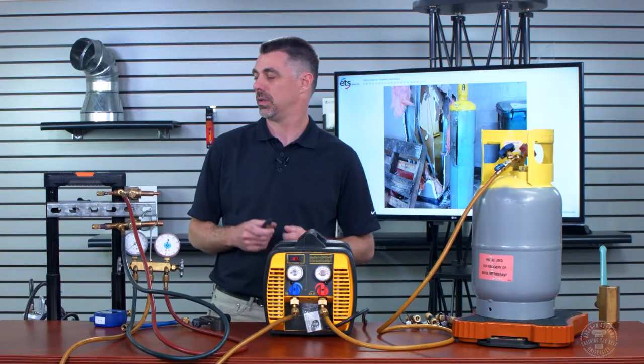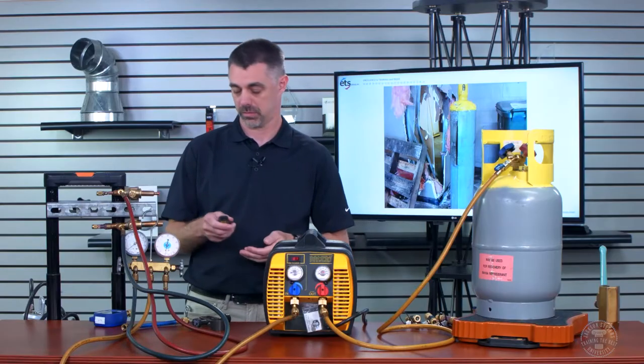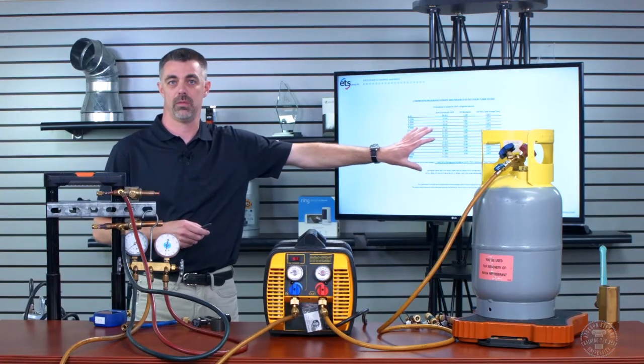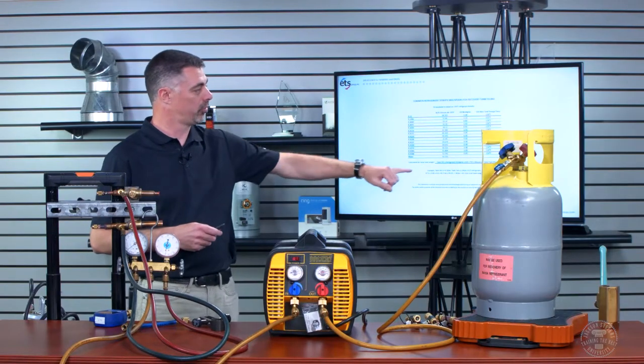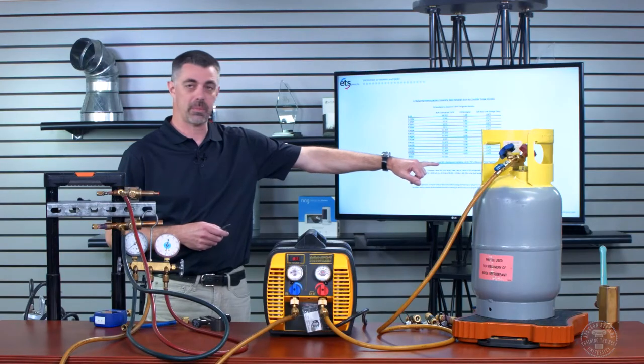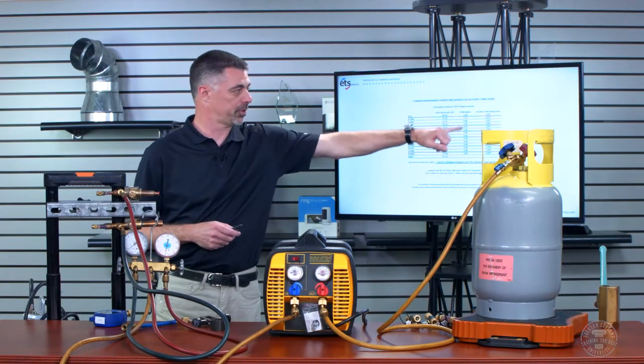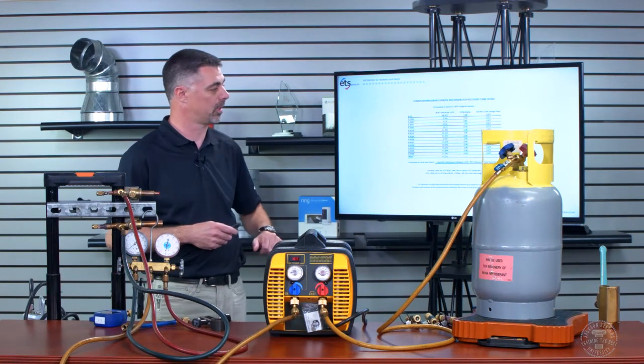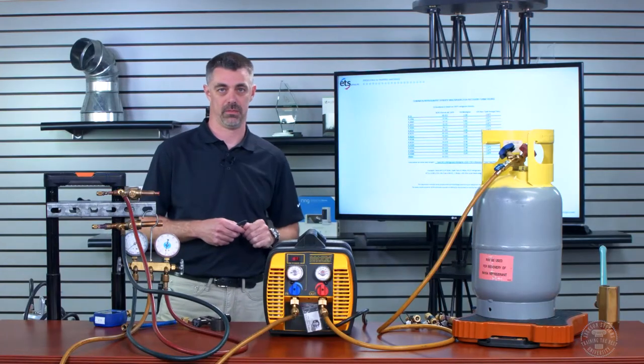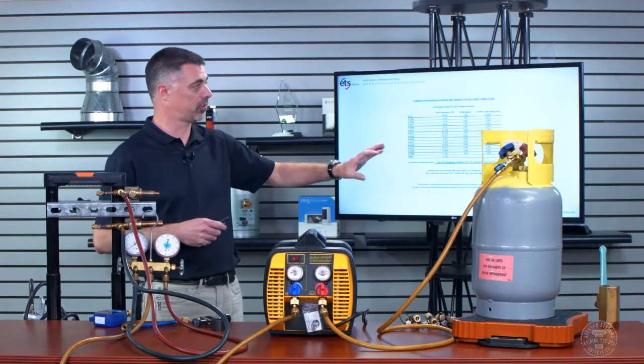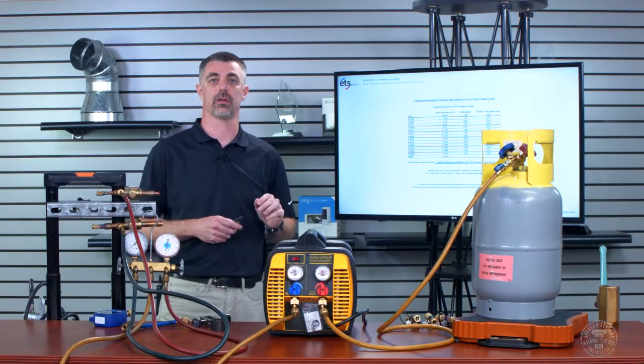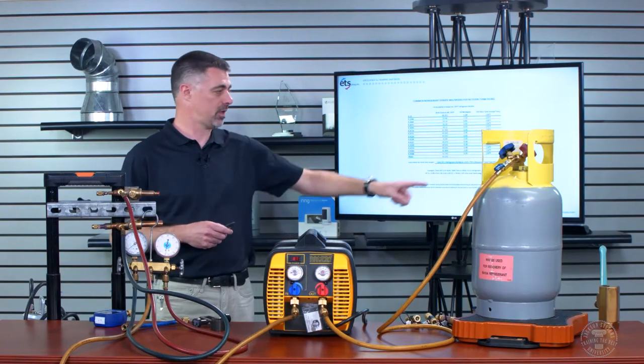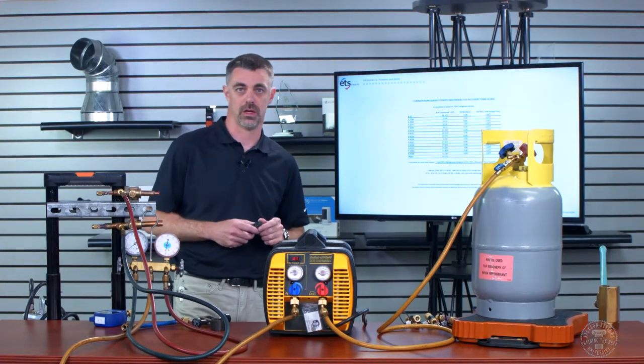To recap the formula: tank water capacity × refrigerant fill multiplier for that specific refrigerant × 0.8 = maximum refrigerant weight. Make sure you use the correct refrigerant multiplier. If the tank will be stored above 130°F, use 0.6 instead of 0.8. That note needs to be added to the downloadable sheet.